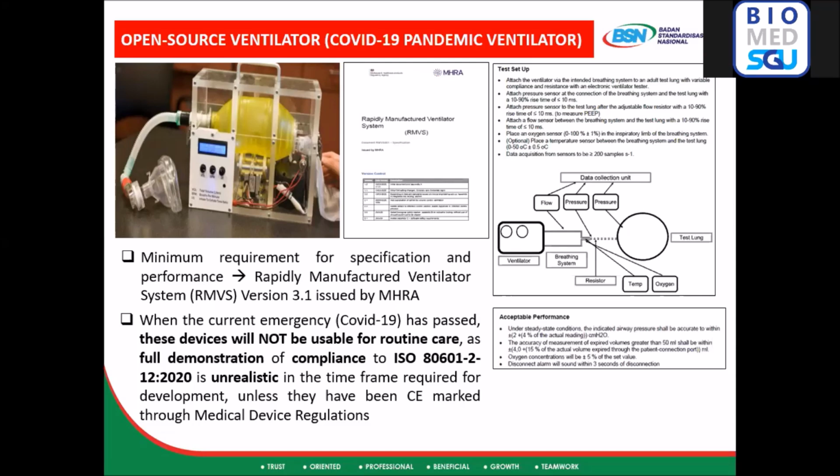Yes. So for medical devices, for example in the case of the open source ventilator, all have to be tested and calibrated by BPFK, which will test them according to the standard determined by BSN. So it is not all handled by a single body, to make it clear to the audience.